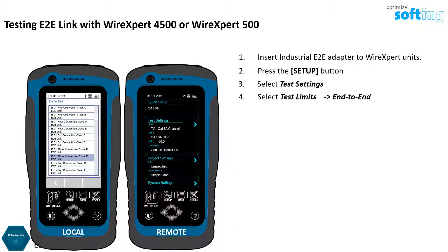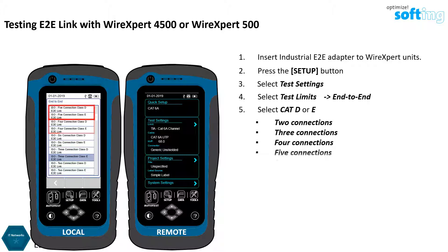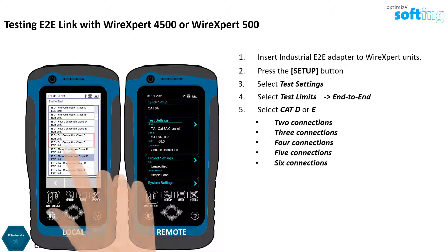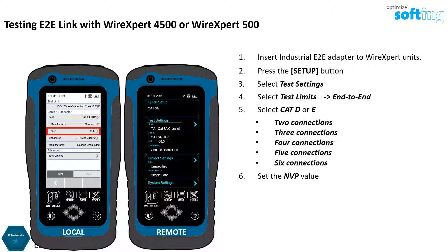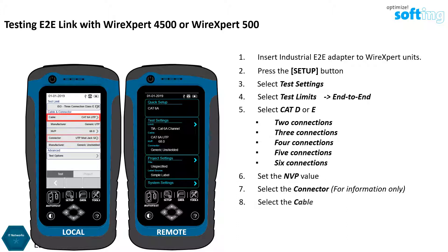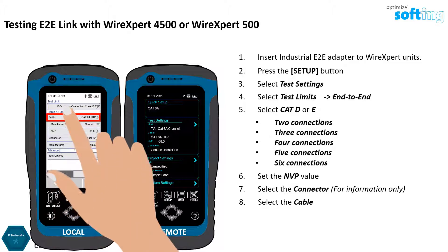Depending on the measurement category — Class D or Class E — select 2, 3, 4, 5, or 6 connections. The correct nominal velocity propagation, or NVP, needs to be indicated to obtain accurate length measurements. Selecting the type of connector is only for informational purposes and will not influence the measurement accuracy.